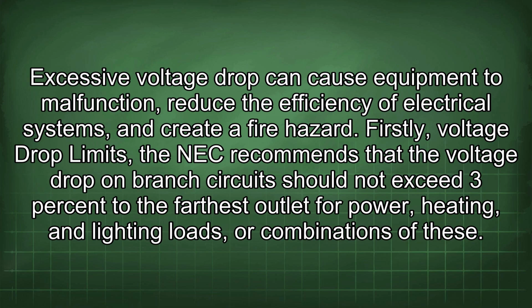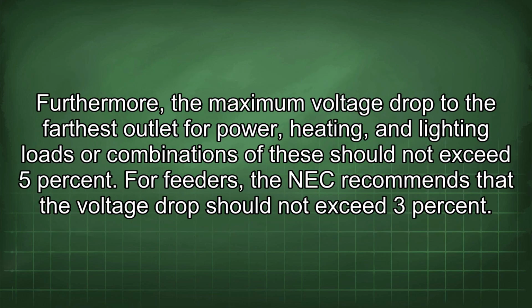Firstly, voltage drop limits. The NEC recommends that the voltage drop on branch circuits should not exceed 3% to the farthest outlet for power, heating, and lighting loads, or combinations of these. Furthermore, the maximum voltage drop to the farthest outlet for power, heating, and lighting loads or combinations of these should not exceed 5%. For feeders, the NEC recommends that the voltage drop should not exceed 3%.